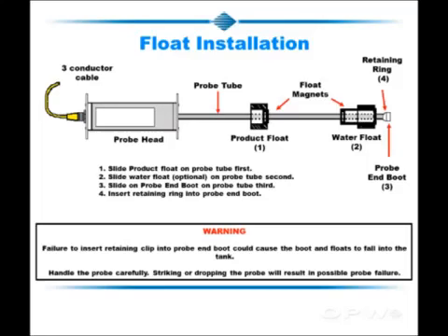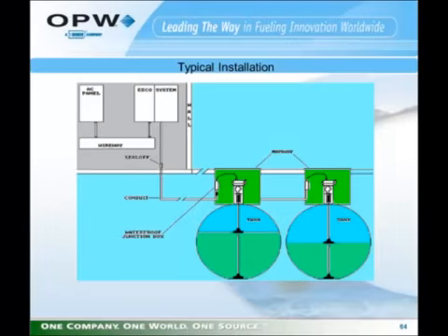If you forget to put the retaining ring on, there's a possibility that the end boot can fall off of the probe when the probe is raised. Both floats would then fall off the probe, and you would have a water float on the bottom of your tank. You would have a product float floating freely in your tank, and you'd have to order new floats for the probe. A typical installation is shown in this diagram.